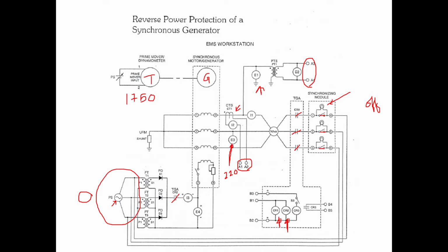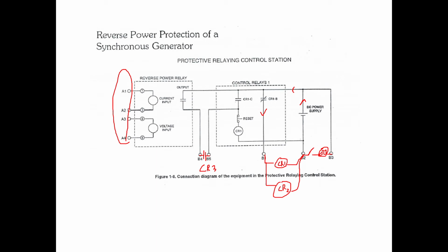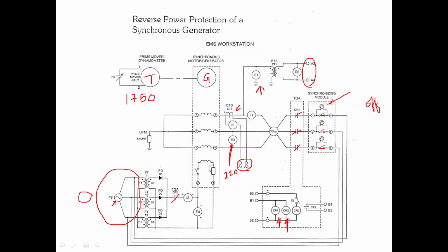Now when you are simulating this fault, when you are turning this power supply and bringing it to zero, the power would reverse. You can monitor the direction of power in the wattmeter. Under normal condition the direction of power will be in this direction, because the generator is supplying power to the grid. When you slowly bring the supply to zero, you can see that the direction will reverse. That means the generator is now starting to work as a motor.